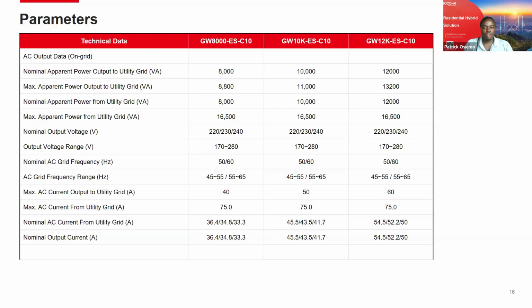Now on the AC ports, regarding sensitivities, you can see the inverter is capable of handling AC grids from as low as 170 to as high as 280 volts. This is configurable during the setting up process. Similarly, the frequency is also configurable. It handles 45 to 55 hertz, minimum and maximum.